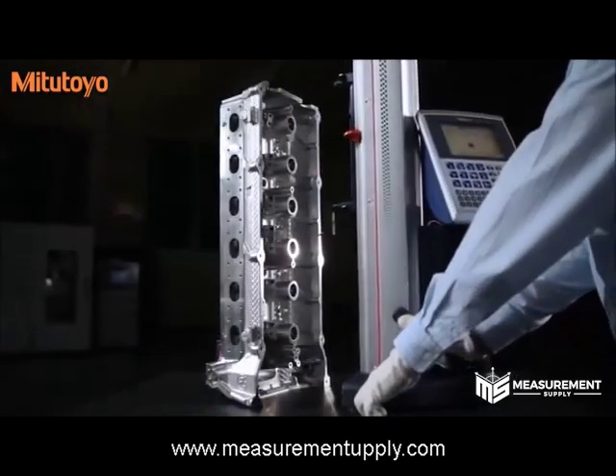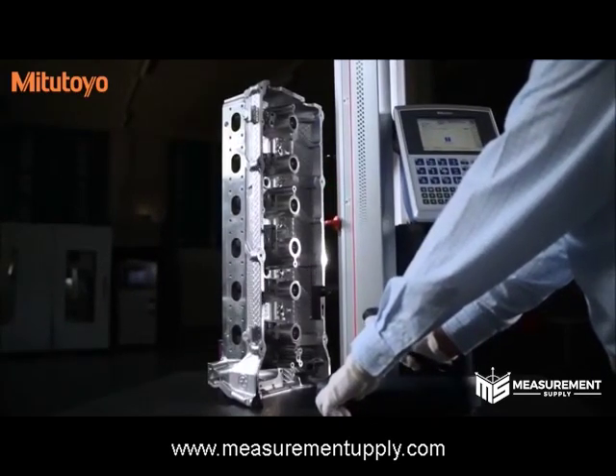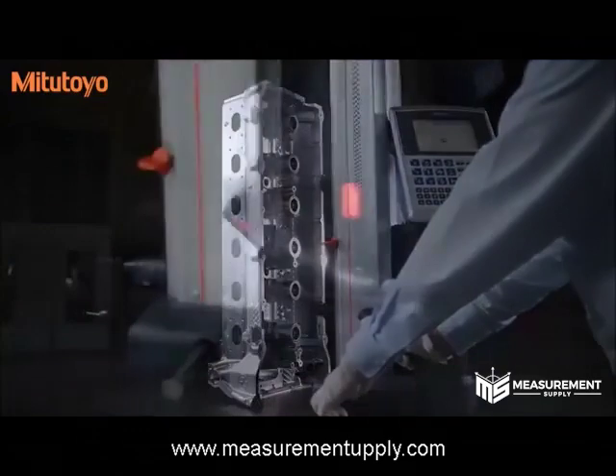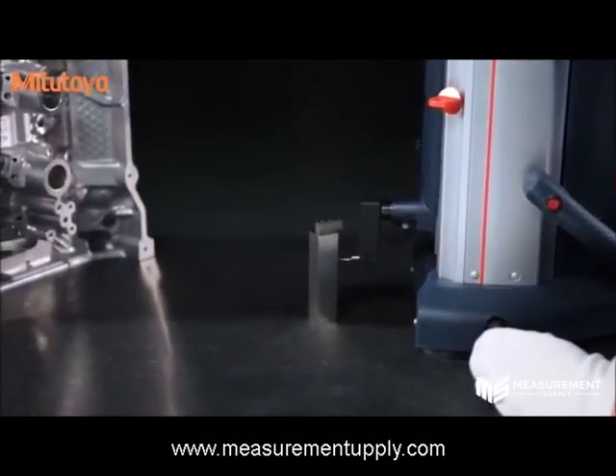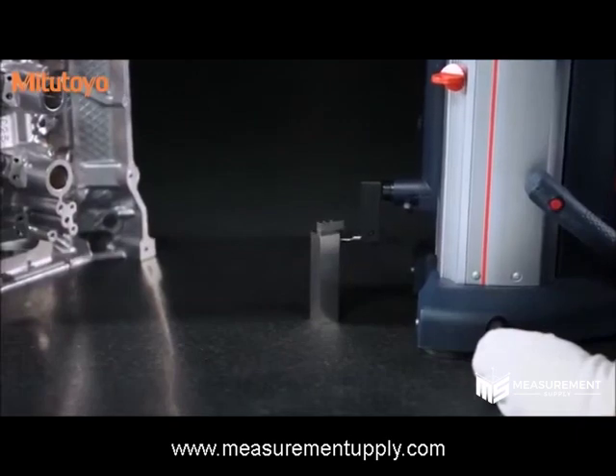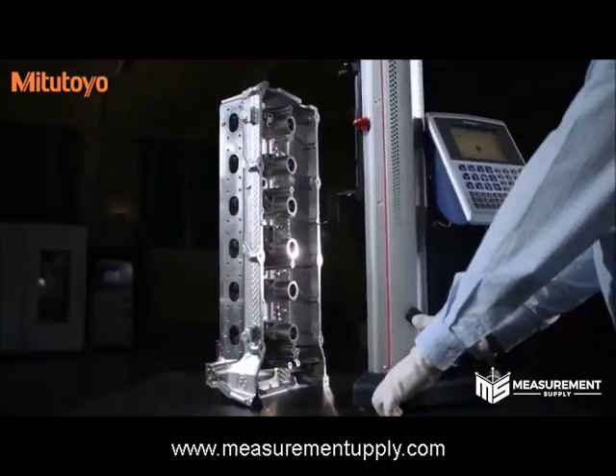With a measuring range of 0 to 38 inches and a 24-inch stroke, the LH600e provides highly accurate 2D measurements. The pneumatic system is mounted on floating or semi-floating bearings that enables the height of the air cushion to be set according to the mode of operation, thereby producing high test speeds without sacrificing accuracy.